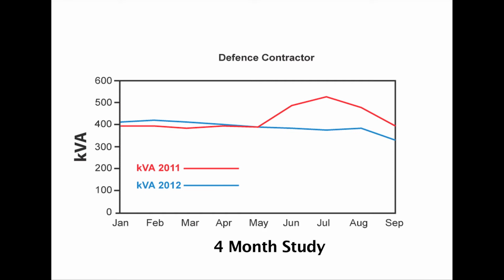Comparing the demand in kVA between January and May, it is evident that the demand for both years was pretty much the same. That was before PowerGuard was commissioned. But after May, the graphs diverged dramatically, indicating a huge increase in demand during the winter months for 2011. What is significant, though, is that PowerGuard prevented peaks of more than 100 kVA from developing.